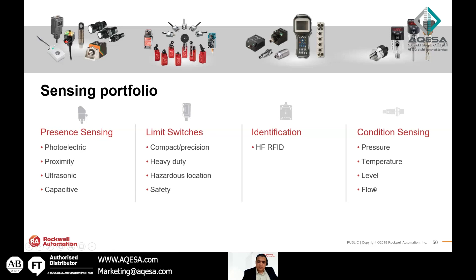Safety again - SIL 3, machine safety. We have safety relays, safety trip devices, emergency stop, pull cable pull e-stop, limit switch. We have presence sensing like light curtains, laser scanners, mats, or edges, so you can detect where a person is to trip the machine in case of SIL 2 issues. We also have safety switches - a lot of types like guard locking, so you don't allow people to go inside the machine or any door unless it's allowed by the safety system.